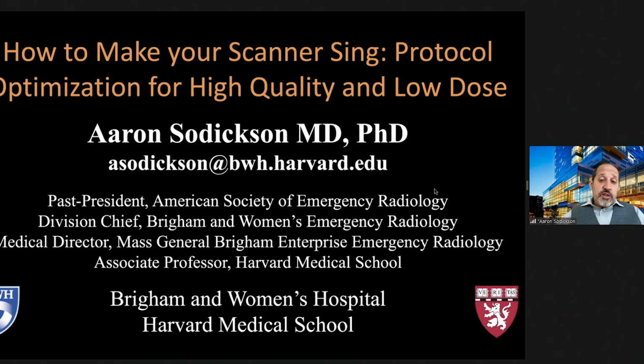I know the Siemens scanner is better than the others, and in this example for the head, they do this flying focal spot, where they move the focal spot back and forth to increase the z-axis resolution, and that does not work at the very high gantry rotations. So there are a few caveats like that that you need to engage your applications people for to figure out really what the fastest scan modes are that are appropriate for your scanner.